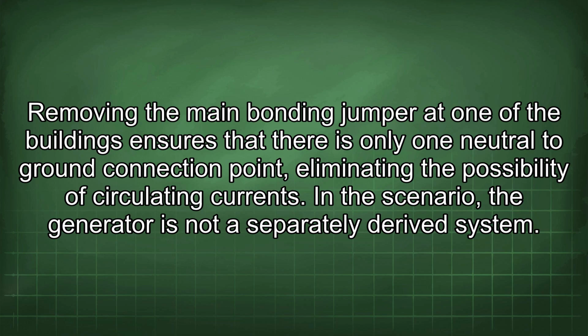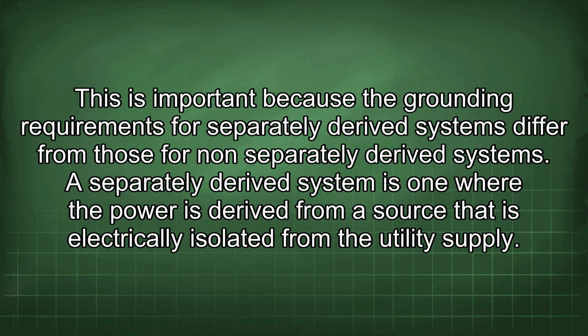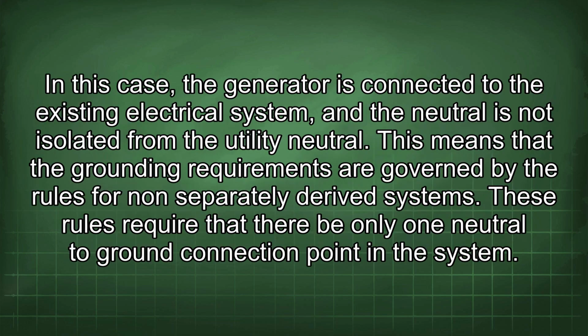In the scenario, the generator is not a separately derived system. This is important because the grounding requirements for separately derived systems differ from those for non-separately derived systems. A separately derived system is one where the power is derived from a source that is electrically isolated from the utility supply. In this case, the generator is connected to the existing electrical system and the neutral is not isolated from the utility neutral. This means that the grounding requirements are governed by the rules for non-separately derived systems. These rules require that there be only one neutral to ground connection point in the system.